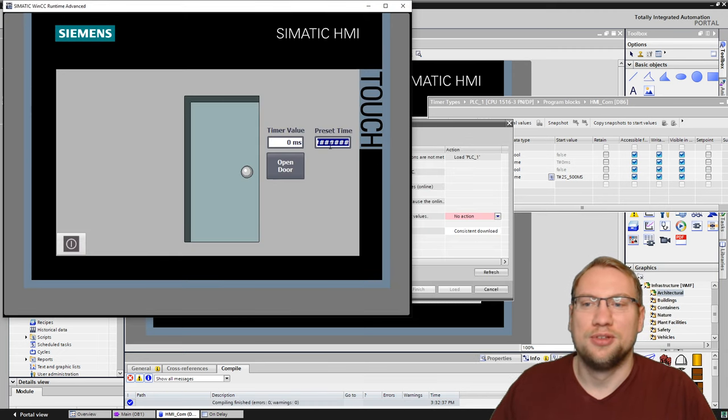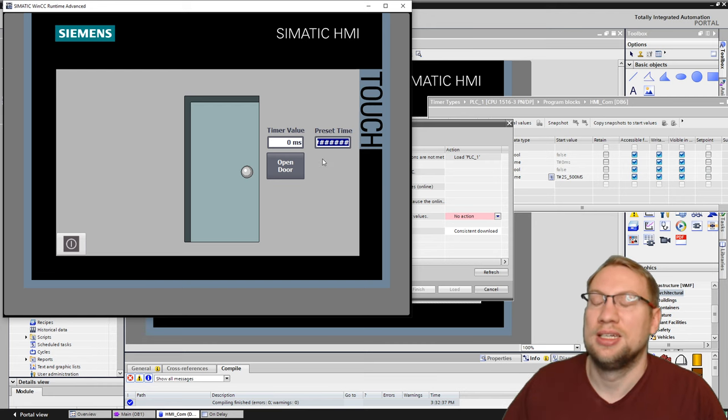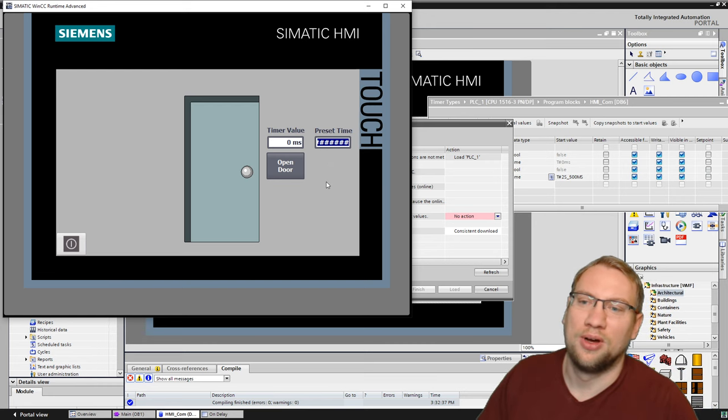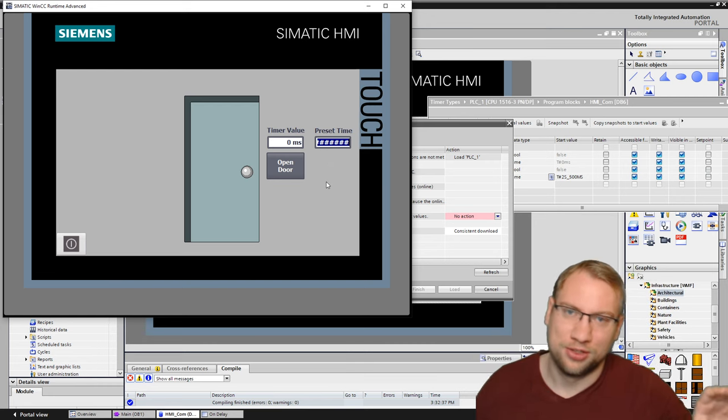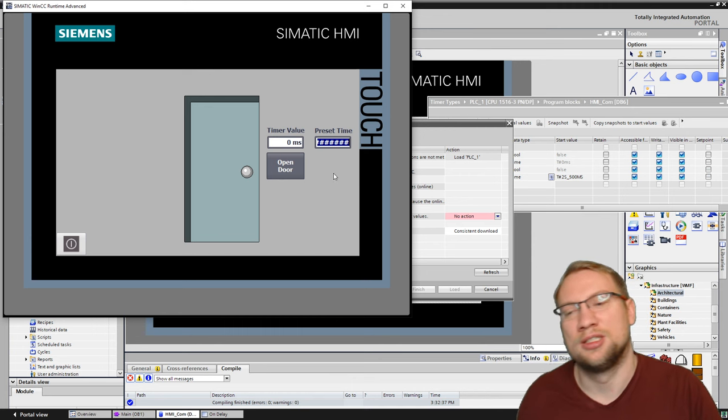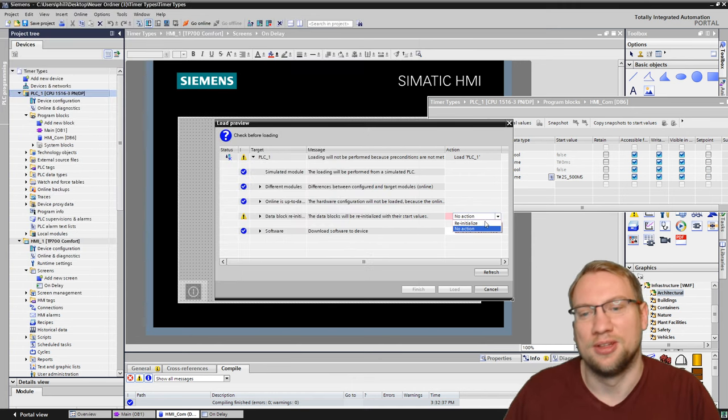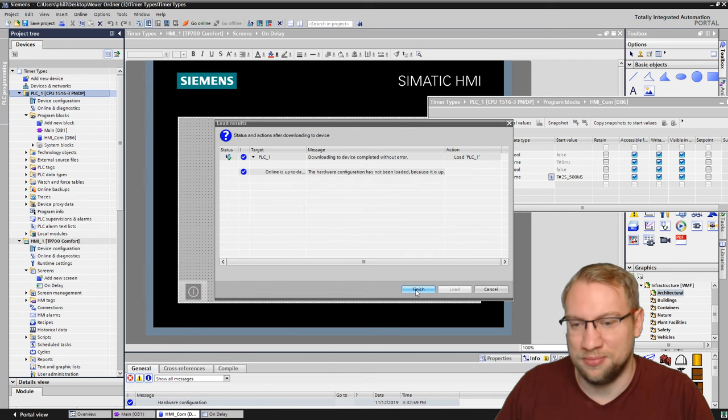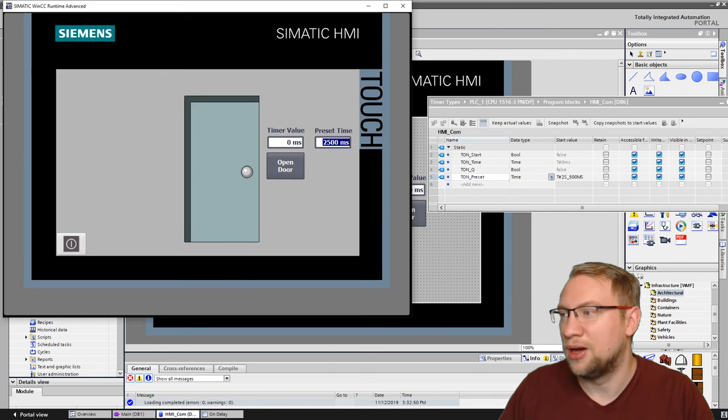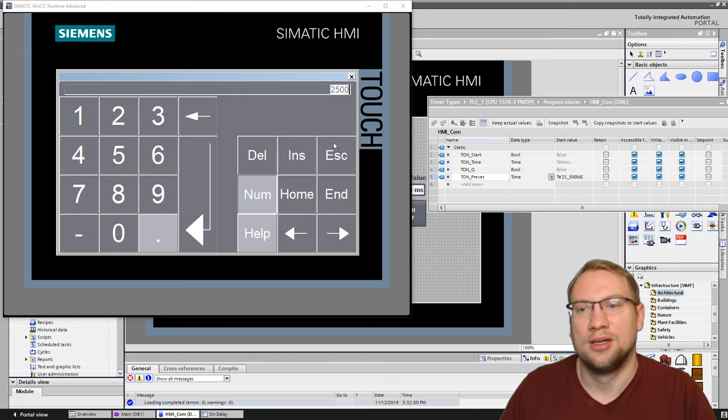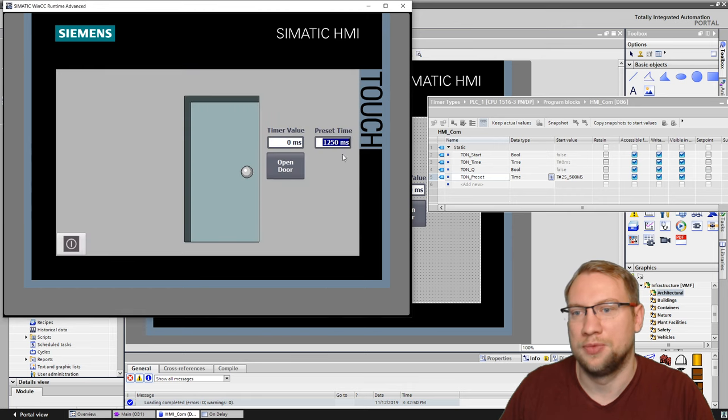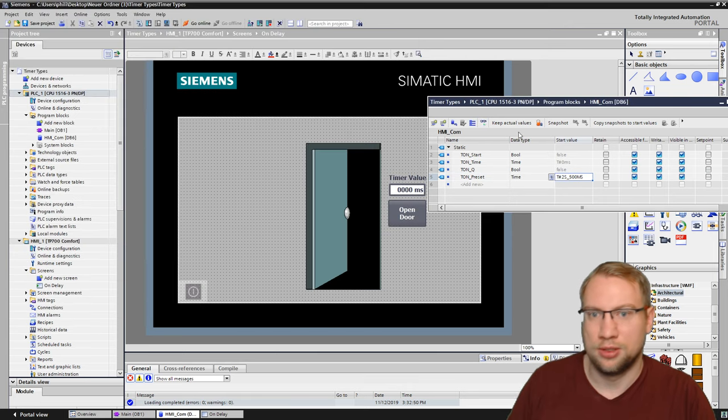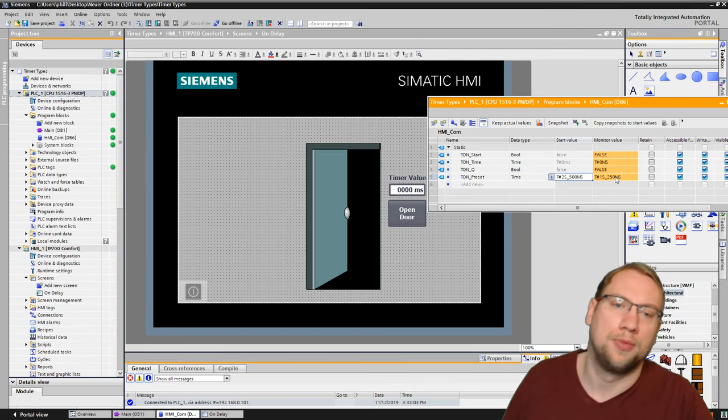If you see those hashtags, pound signs, those hashtags, you know that this variable does not have a connection to the source where it gets the value from. That's because I haven't downloaded the PLC program yet. So I also got to do that. And now those should be gone. And I can see 2,500 milliseconds. Great. I can also change that. Like 1,250. I can change it. And it should also be changed in here. There we go.